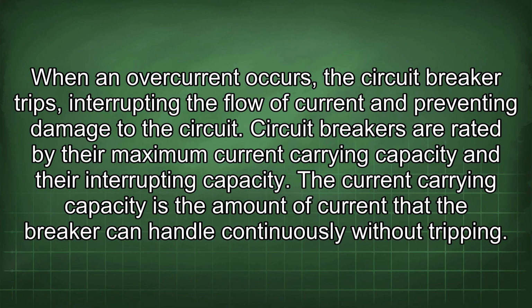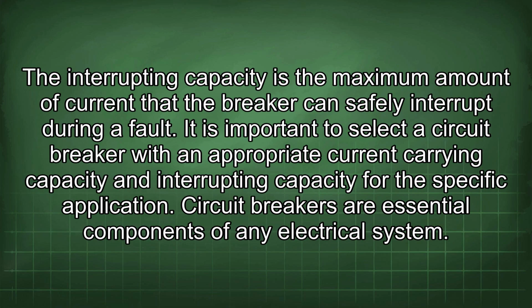Circuit breakers are rated by their maximum current carrying capacity and their interrupting capacity. The current carrying capacity is the amount of current that the breaker can handle continuously without tripping. The interrupting capacity is the maximum amount of current that the breaker can safely interrupt during a fault. It is important to select a circuit breaker with an appropriate current carrying capacity and interrupting capacity for the specific application.